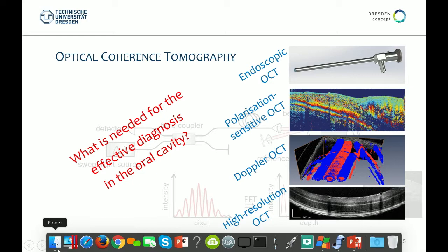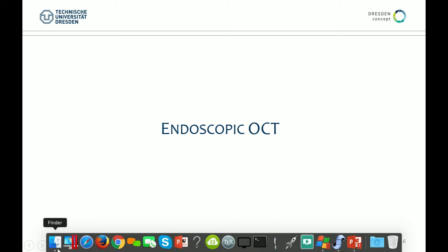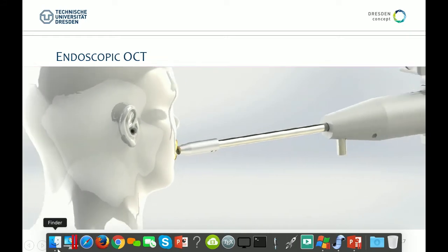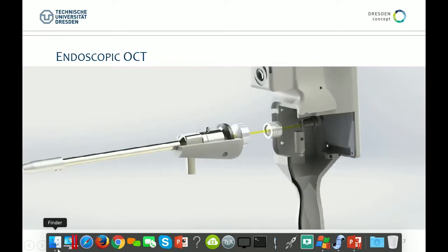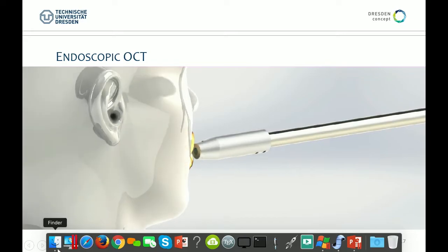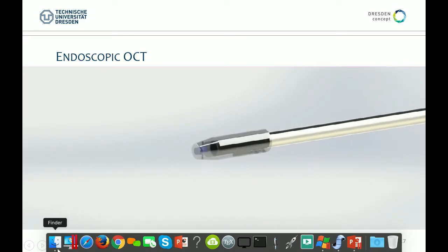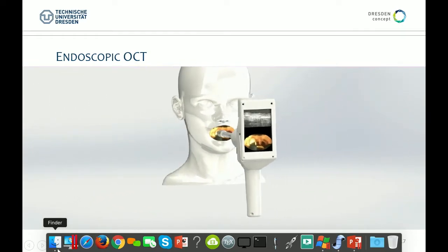We have blood vessels within the connective tissue and lamina propria, collagen fibers within this connective tissue, and the hard dental structures are highly birefringent as well. We definitely need an endoscopic OCT adaptation. This is our latest development of an endoscopic scanning device. The key is that we use a commercial endoscope from the company Storz in Germany, with adapted optics in front and a mounted camera, using an LCD screen for video guidance during investigation.